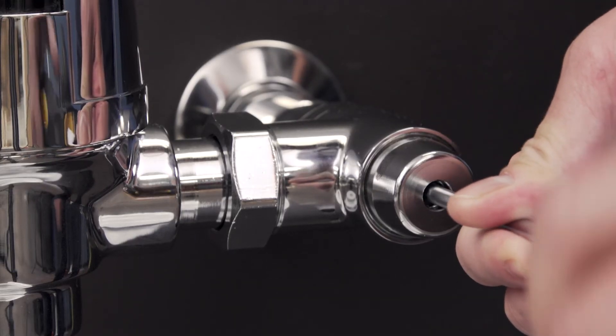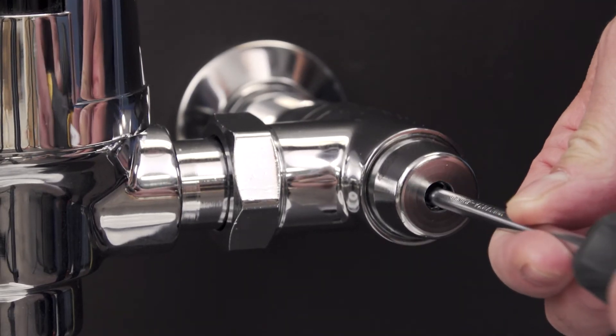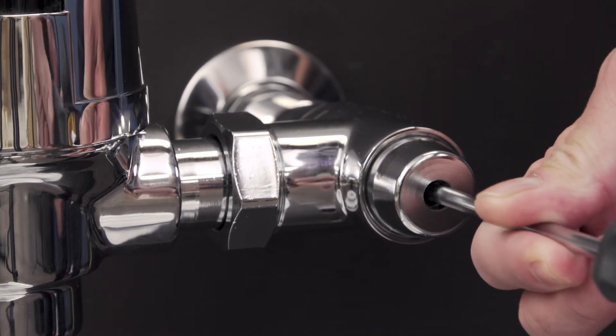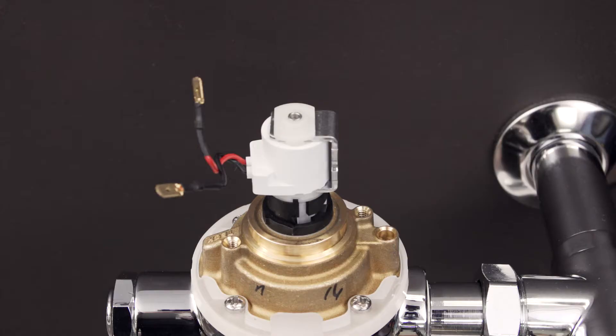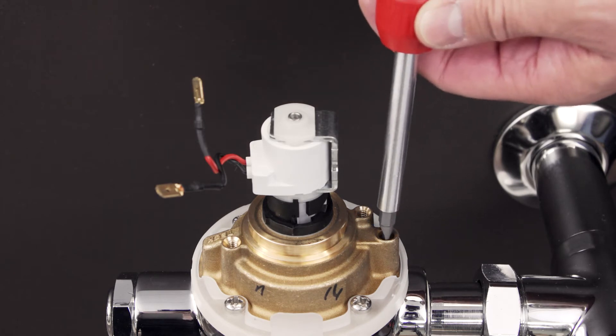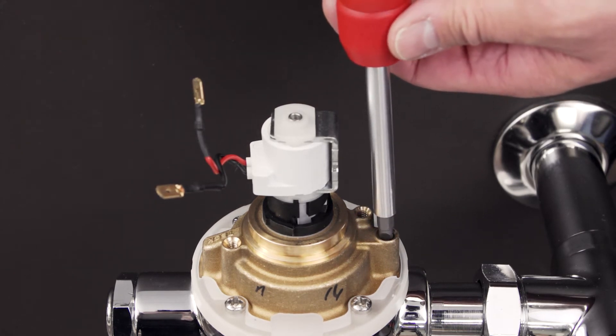If there's an excessive amount of water coming out during each flush, then first check the inlet stop. Close the inlet stop valve all the way, then open it one complete turn. Check the position of the regulating screw and make sure that there are no obstructions.